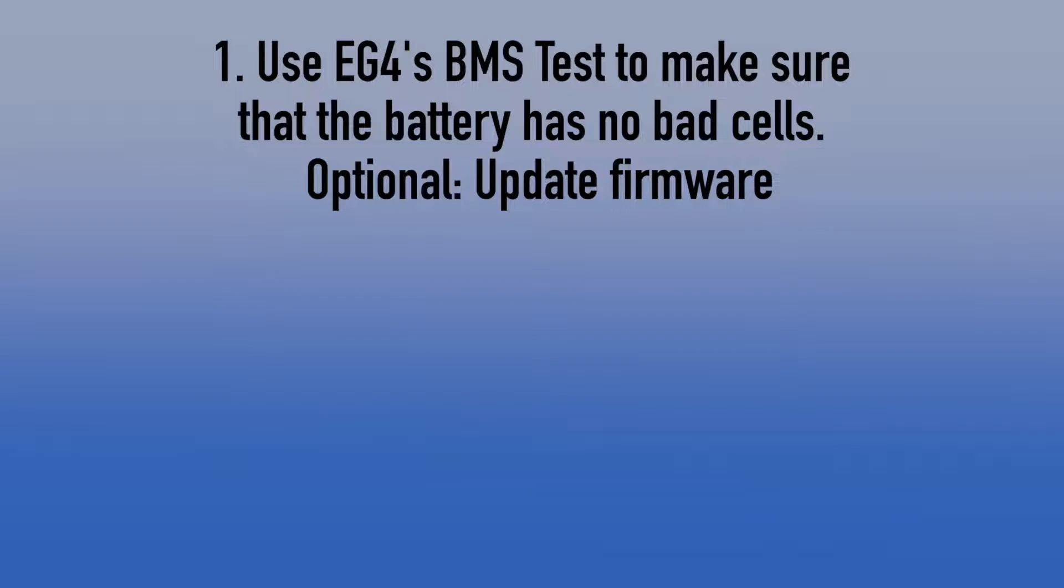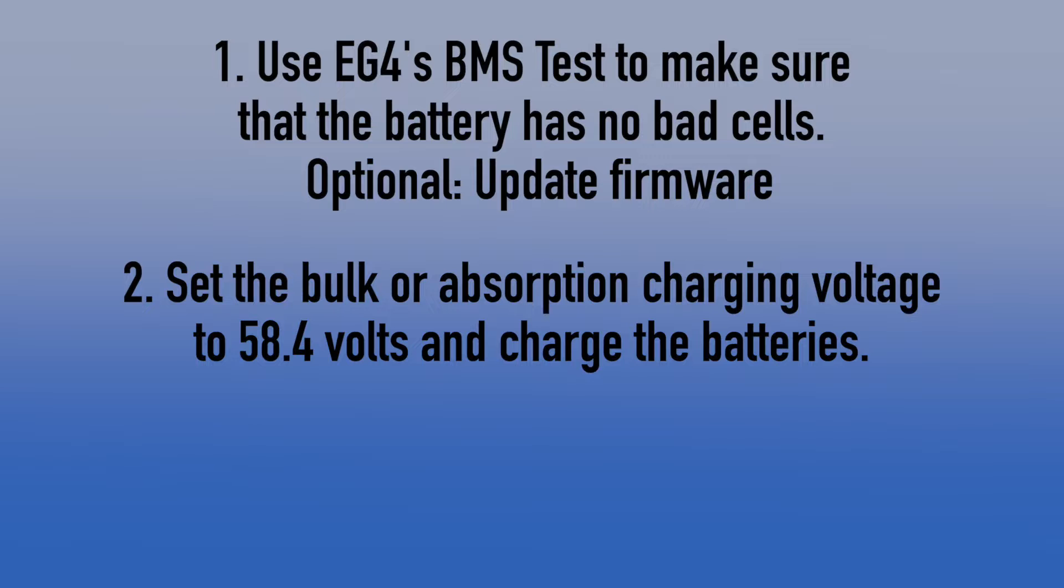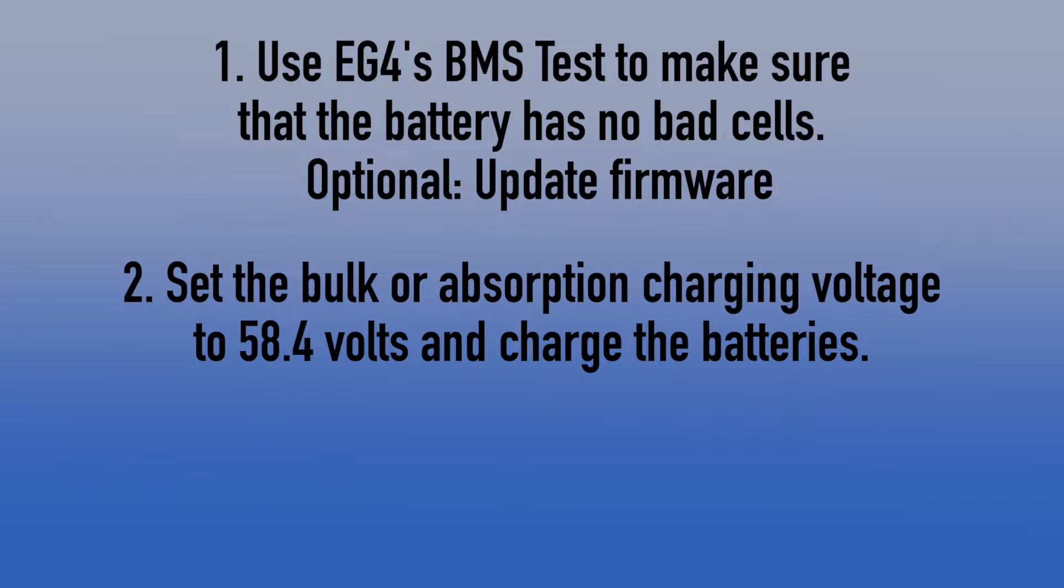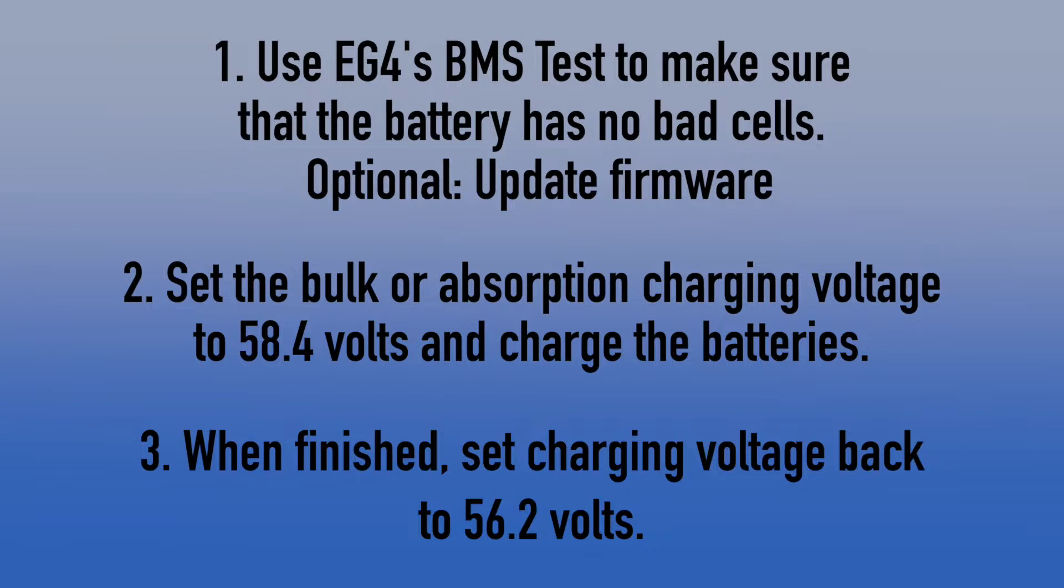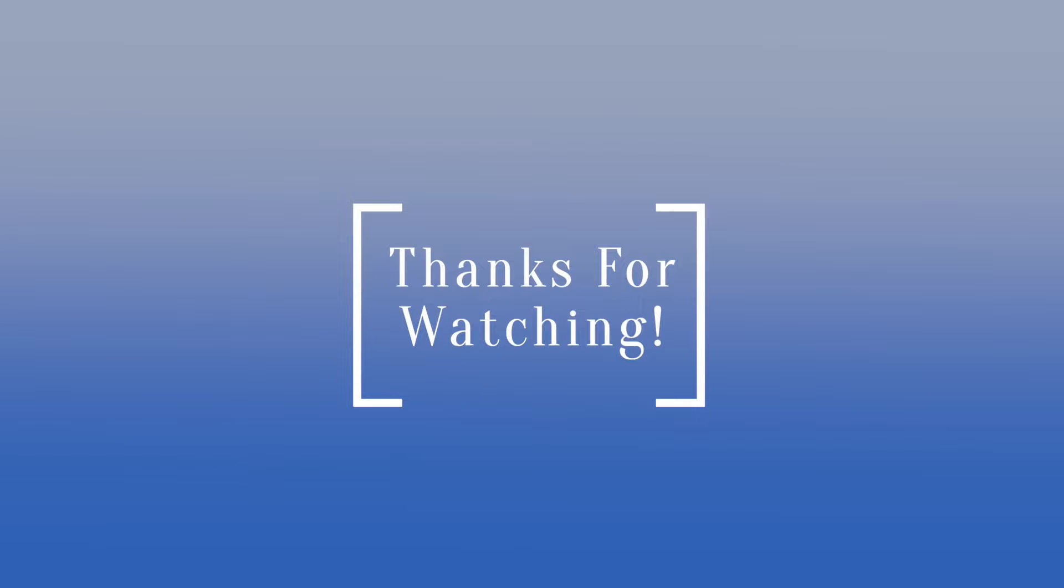Let's just review. First thing you do is go to EG4's website, download BMS test, and you want to make sure your battery doesn't have any bad cells, anything that's way out of line with the other cell voltages. That's a different problem, and this is not going to solve it. Optionally, you can also upgrade your firmware. I would recommend doing that, because it's added a lot of new features. Then you just set the bulk or the absorption charging voltage to 58.4, and charge the batteries. When you're done, you just want to set your charging voltage back to its normal 56.2. I hope this helped some people. That's it for this video. I'll see you in the next one.